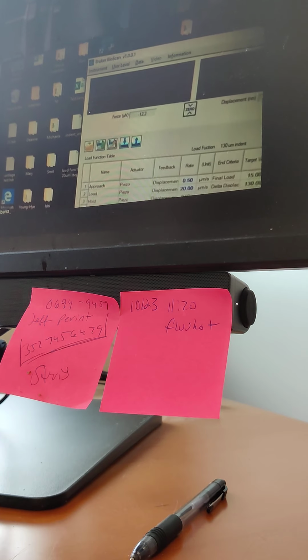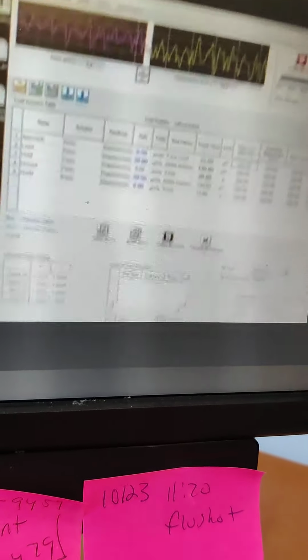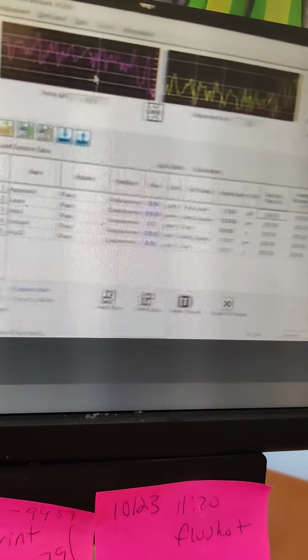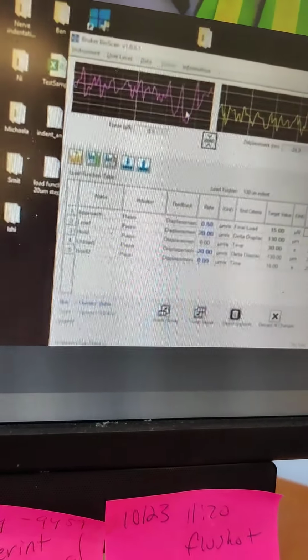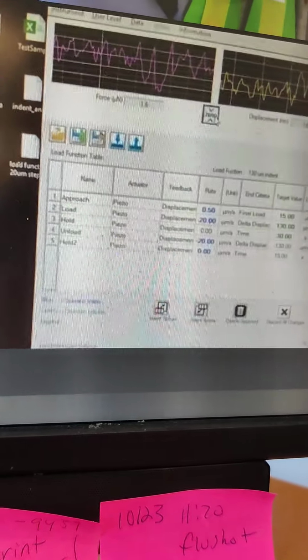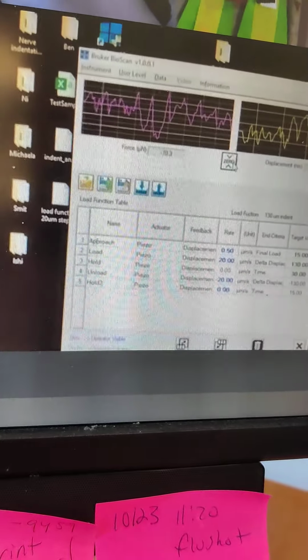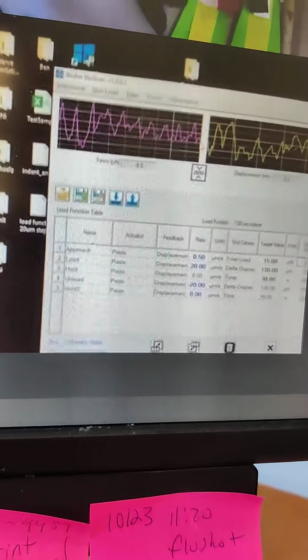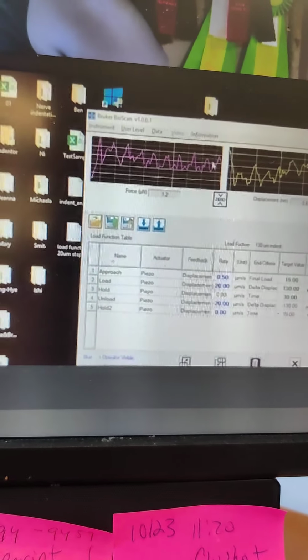All right. So for step 4, for running your samples, it says check the force is approximately 0 newtons. So what it means is that you have to make sure that the force curve here is centered at 0. So the running average is 0. Okay. Right, and if not, then you can always change the piezo bias here, which automatically pushes it up or down. Okay. So can you press that 0 button? And then it'll center it to 0, maybe? Yeah, it should automatically center it, and you can't really see the difference, apparently. But it's a very minute difference. Yeah. It doesn't change how high or low it goes. It just changes the centering.